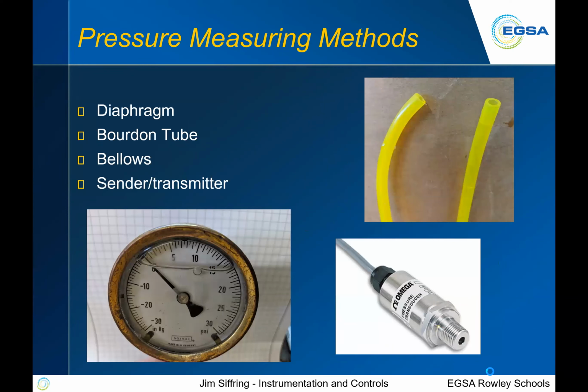So let's talk about measuring pressures, all the different methods we can use to measure pressure. Diaphragms, Bourdon tubes, bellows, sound senders, transmitters, things such as that. Lower left, you'll see a Bourdon tube gauge. Over on the upper right, you'll see a piece of tubing. What in the world do we use a piece of tubing for measuring pressure? Notice in that piece of tubing, there's some water at the very tip. I wish I could show you this, but my cursor's not working.